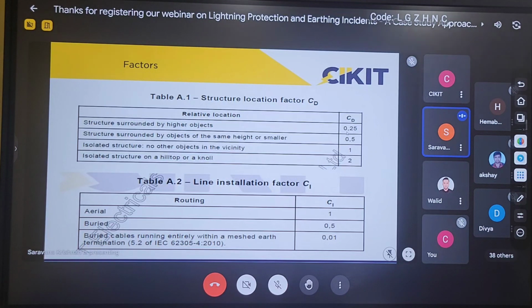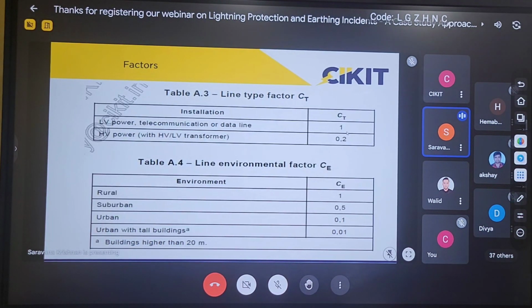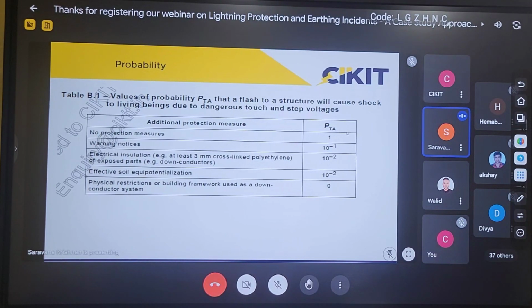Third, line installation. In some areas, even if I want to, I cannot take an aerial line. So there are many practical difficulties involved. All these parameters are constants and we don't have any control over them. The parameters related to the number of dangerous events are all constant, and once determined, we cannot change them. But the next one is the probability. This is the actual region where we can have control for reducing the risk due to lightning.